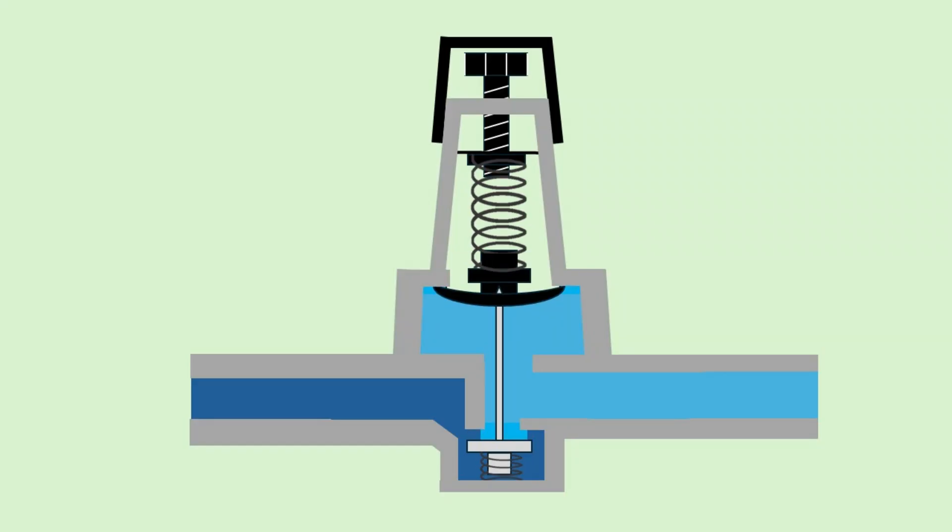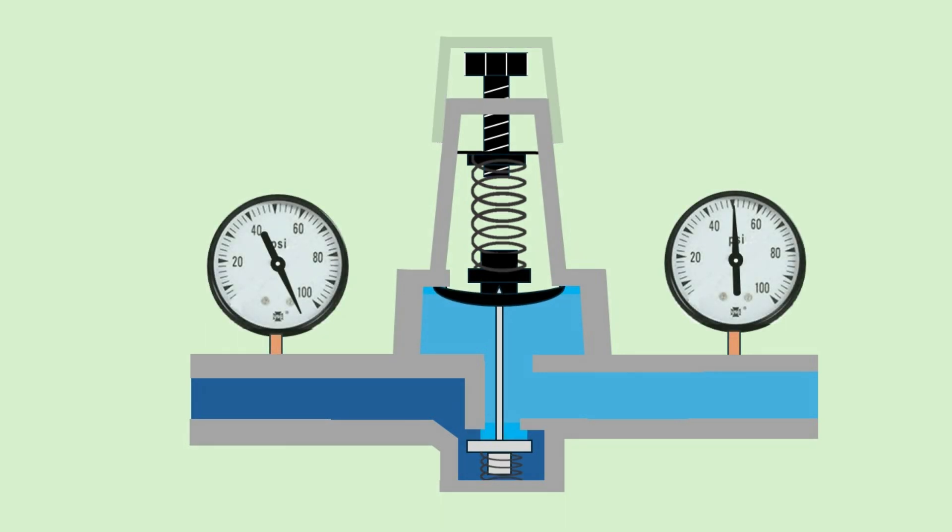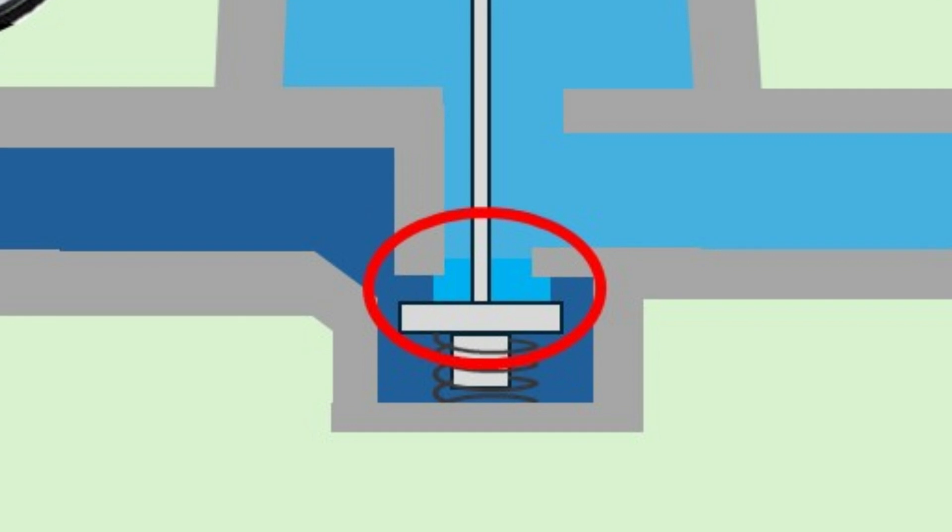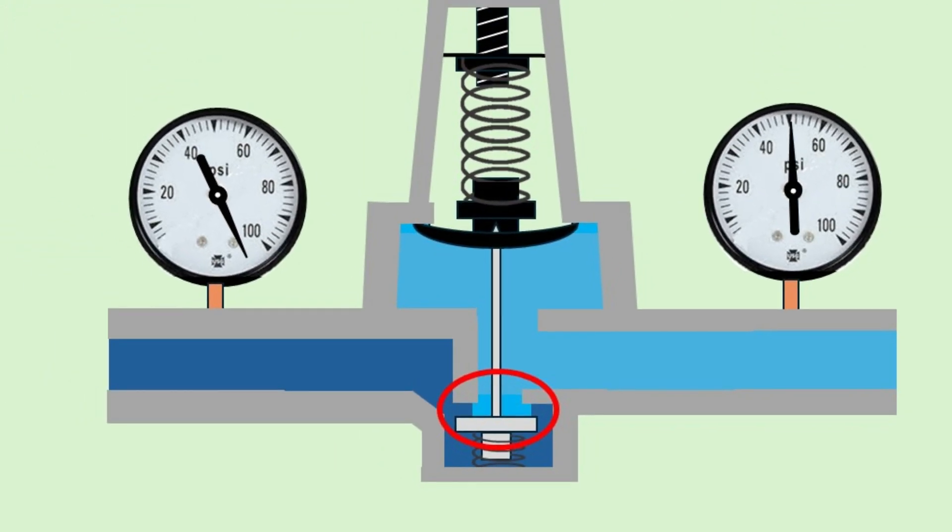Here's a quick look at how the valve operates. As the diaphragm moves, it adjusts the position of the poppet valve, opening or closing the gap to control water flow and regulate pressure. The gap between the poppet valve and its seat is where the pressure reduction happens. As water flows through this restricted opening, the pressure drops.